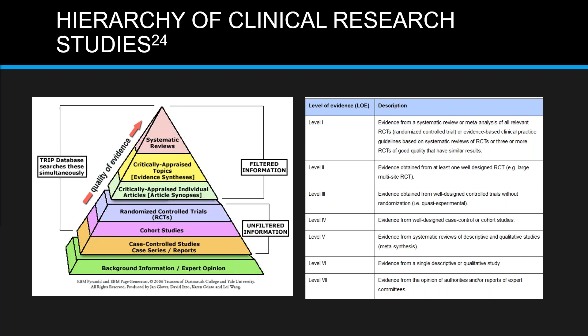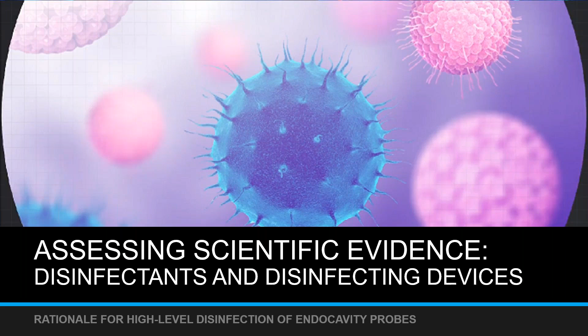Now, what is the rationale? We're going to move on to the rationale for high-level disinfection of endocavity probes and give you some actual data. Next slide, please. First, we have to demonstrate the efficacy and effectiveness of a disinfectant or device for disinfection. Efficacy means a study that's done under ideal circumstances. In a clinical trial, that's a randomized clinical trial. Effectiveness means how does it work in real life situations? So we want to demonstrate that a disinfectant or a device inactivates microbes that you would inoculate onto a surface of medical devices.